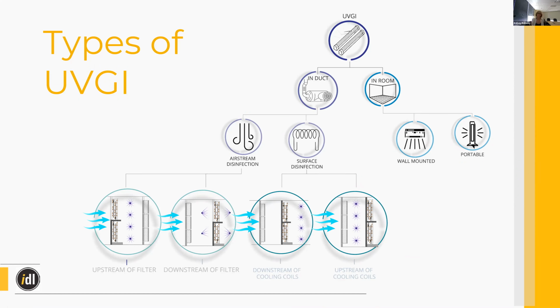To break down that nuance a little bit more, because at least for me, I was like, oh my gosh, there are so many different ways that UV is used. Like I said, it's either in your duct or in your room. If it's in your room, it's mounted on the wall above your head, or sometimes there are portable lamps that you will see in operating rooms when they're not occupied. But in duct, you can shine the UV light on your cooling coils and disinfect the mold buildup there. But you also see it disinfecting the airstream itself. So each takes a different irradiance, and a different speed or velocity of air going through.